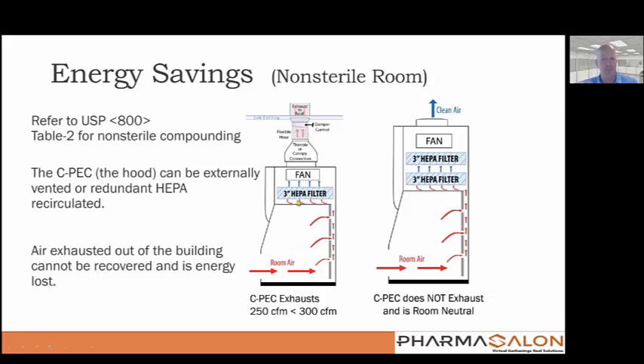But I can tell you, from many years in this business, these are fickle animals. My preference is that if you've got the budget, $7,000 or $8,000 will then get you into what's called a redundant HEPA filtered series, which means I've got two layers of HEPA before it goes out of the building. Then I can recirculate this air back into the non-sterile room, which means that this hood is now not contributing to the negative pressure. It's room neutral.